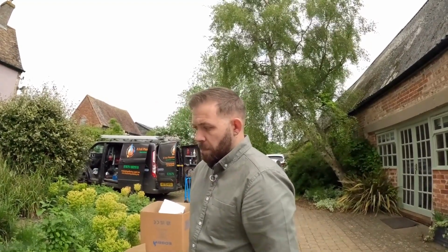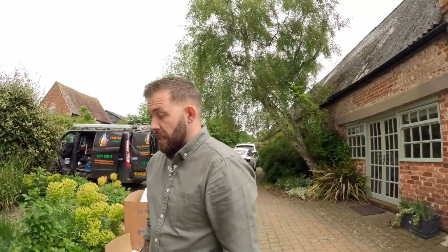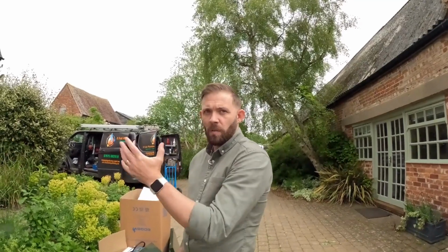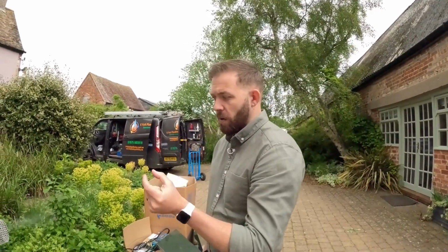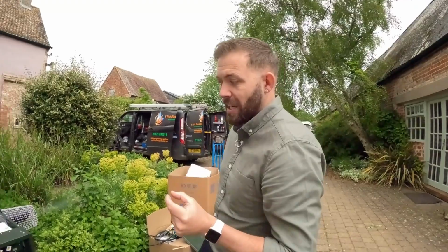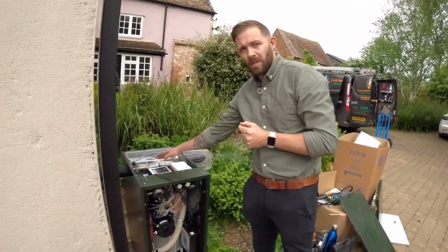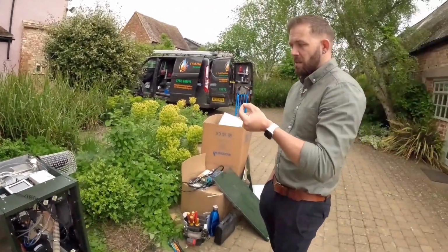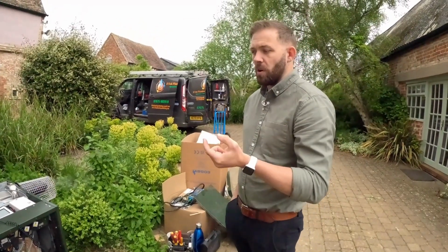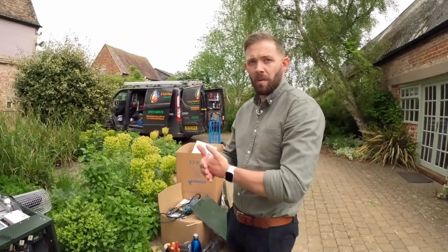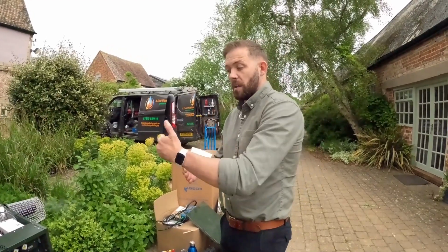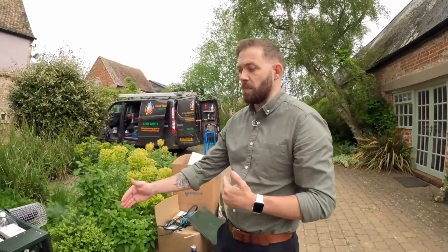Okay, perfect. You were saying earlier as well, it will still save a little bit of energy efficiency over a normal condensing boiler, even on a switch live input instead of OpenTherm. Yes, so even if you take away the OpenTherm with your load compensation and weather compensation, and you just use it on a switch live operation, it will then modulate itself to the PT sensor, so the actual flow temperature. So therefore you are still saving fuel, because you're not coming on and just working at one fixed output. It will come on and then modulate itself to whatever flow temperature you set the boiler to run to in your commissioning screen.